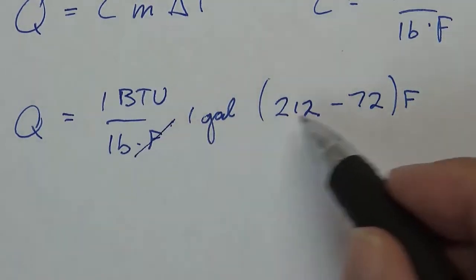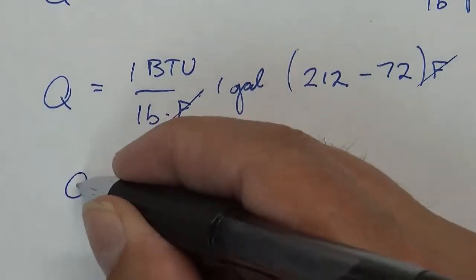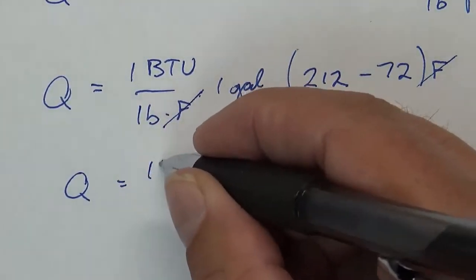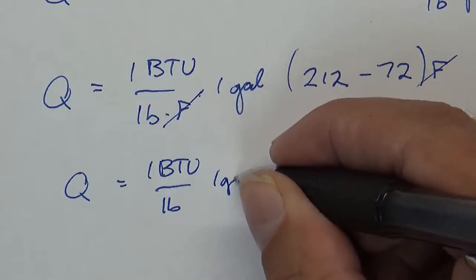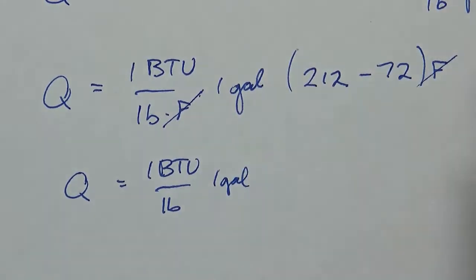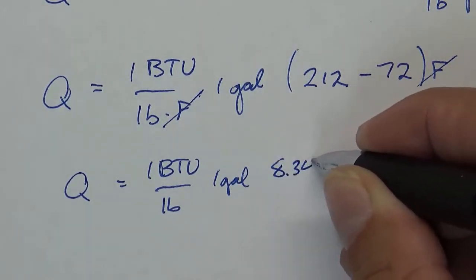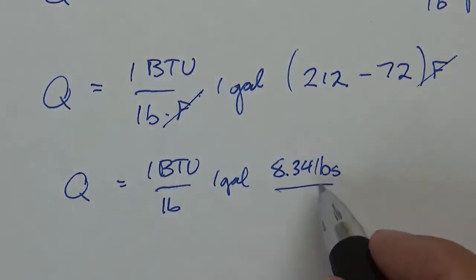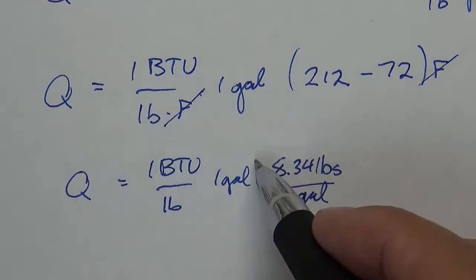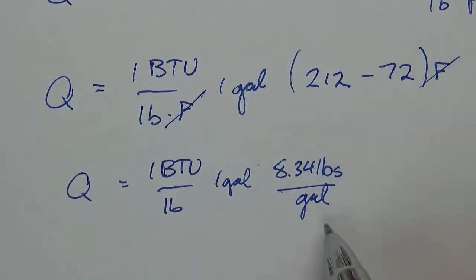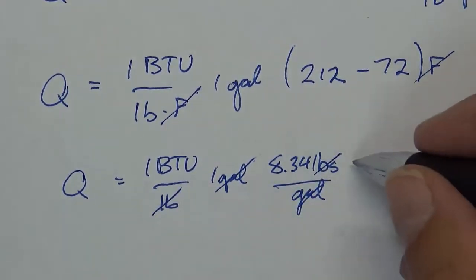So you can see the units of Fahrenheit are going to cancel away, but we've got this problem with the gallons. So let's go ahead and rewrite that. We've got one BTU per pound, we've got one gallon, and I know that one gallon weighs 8.34 pounds. So I can multiply 8.34 pounds per gallon, and that's just like multiplying or dividing by one because 8.34 pounds equals one gallon. The gallons go away, the pounds go away.